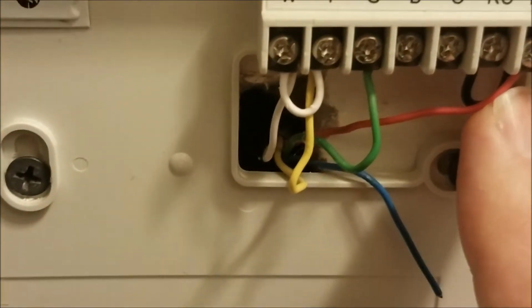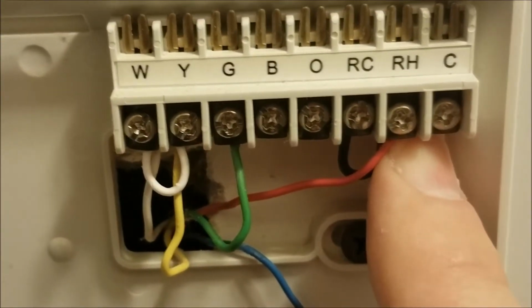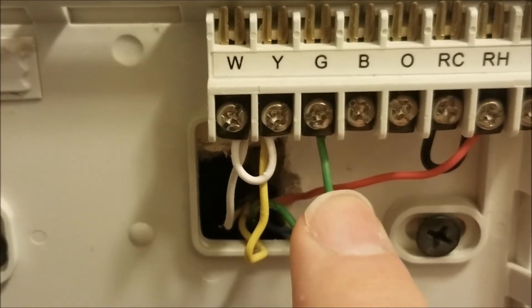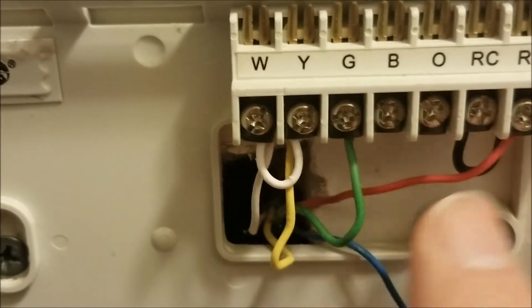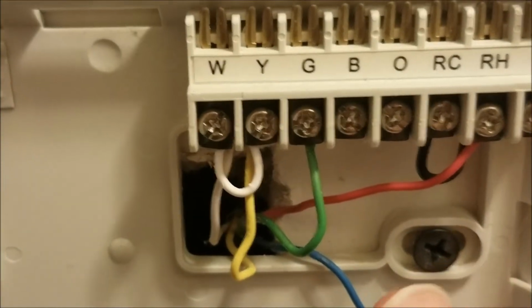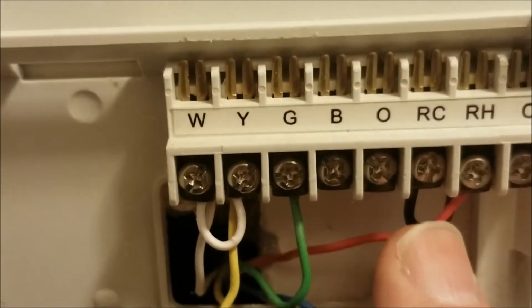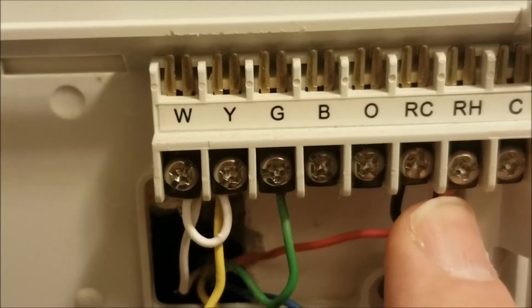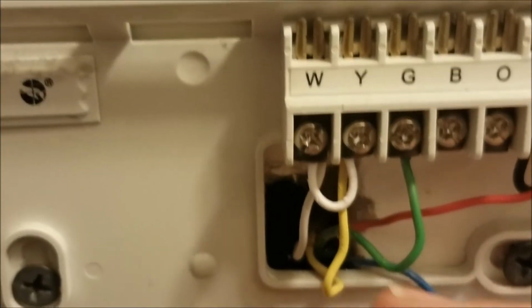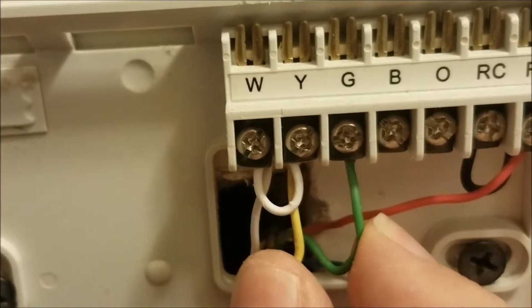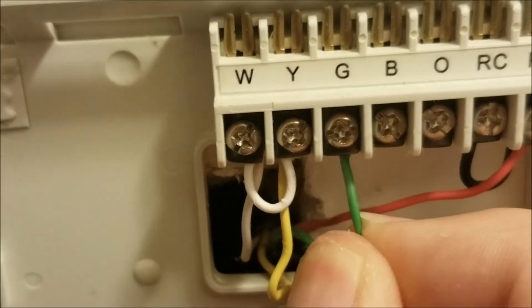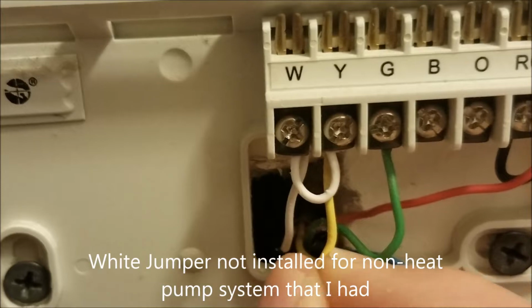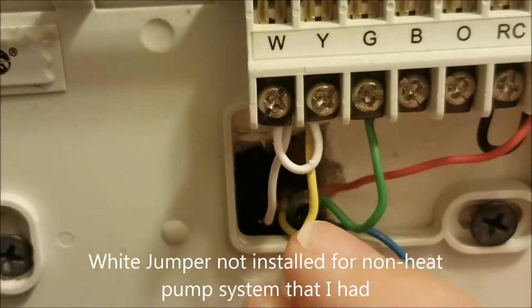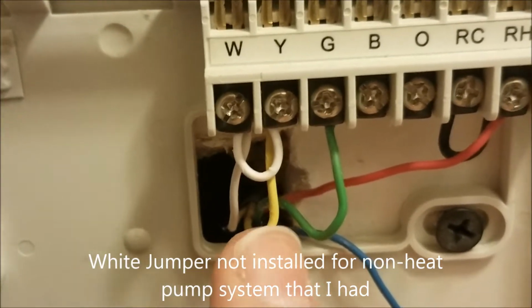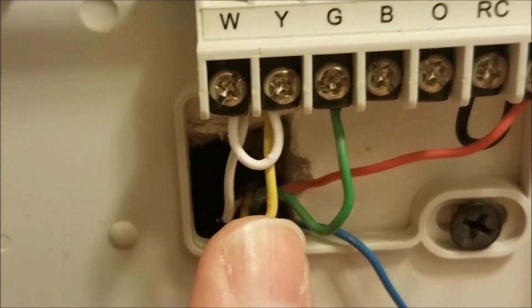So when you're turning the fan on only, it connects 24 volts that comes up here, and then connects it to the green wire which goes to the fan. So that'll let the fan run by itself without the rest of the system. When you put it into cooling mode, it then sends 24 volts through that same relay to both of these wires. So it turns your fan on, and it also turns your compressor on. Everybody's unit is a little bit different, but this will actually go to the control board and turn on the compressor outside, telling it it's in cooling mode.